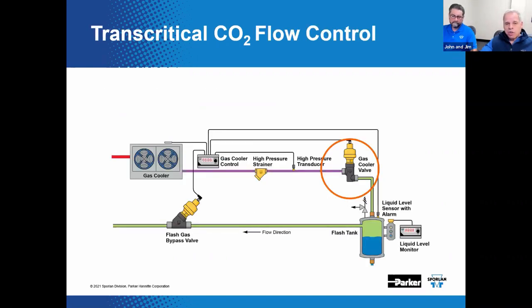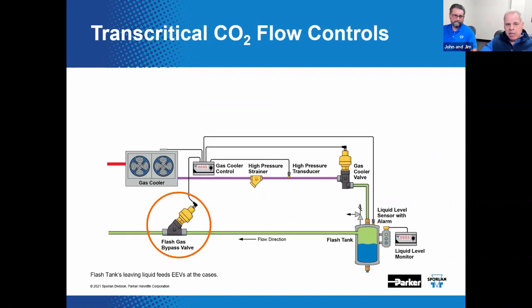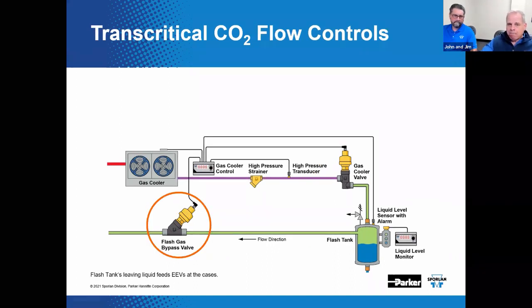Here's a little closer look at the gas cooler valve. The valve is located on the high pressure side. It regulates pressure in the condenser gas cooler, if you will. The CO2 pressure will drop as it flows through the valve. The valve outlet typically is connected to the flash tank receiver at an intermediate pressure. Now here we've got the flash gas bypass valve.